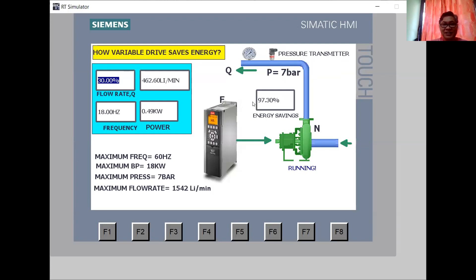If I reduce to 30% flow rate demand, you actually have an energy savings of 97.3% and your power is only 0.49 kilowatt.